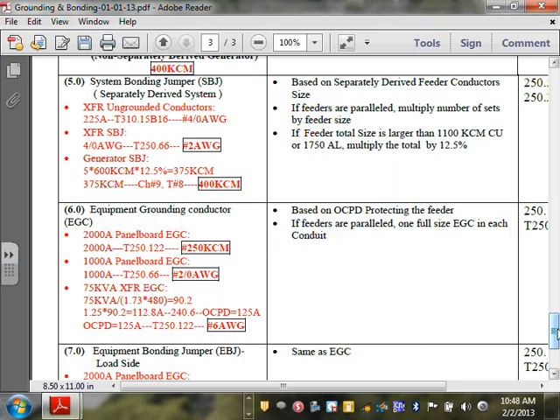I'm sure a lot of you are familiar with that one. Your equipment ground conductor cannot be paralleled. You have to pull one full size with every run. Okay, so take this example. I have a 2,000 amp panel. I want to size it.